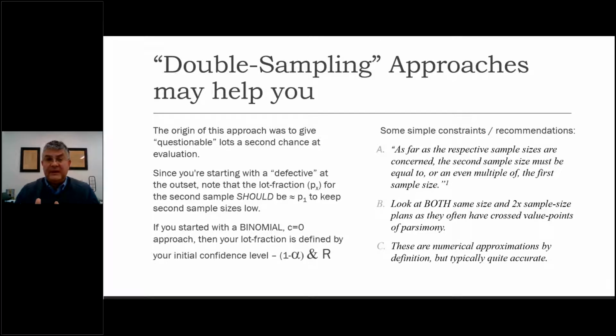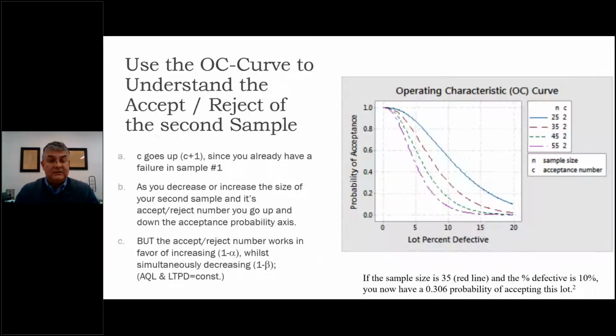But it's important to do that because if you do, the fidelity of the results coming out to you are meaningful. If you don't, there's an entrenched error in there that you have to watch out for. So keep it straightforward. Just keep the same augmentation sample size or a multiple thereof, okay? That's why it's important to know the cost of each additional specimen, right? Usually there'll be pressure to keep it low. Depending on where you are on the OC curve, that's going to make a big difference. So let's move forward and take a look at what that means.